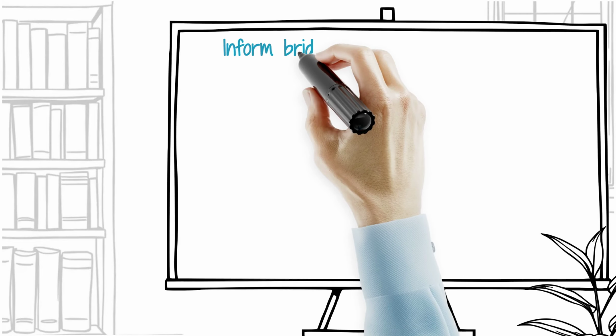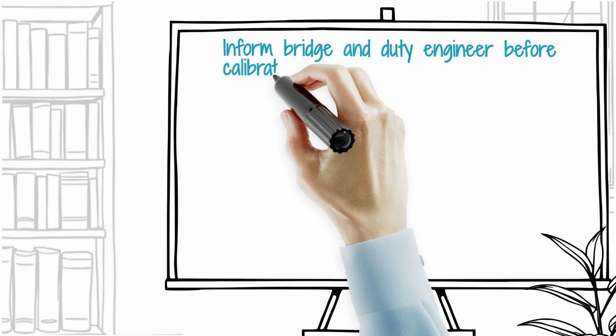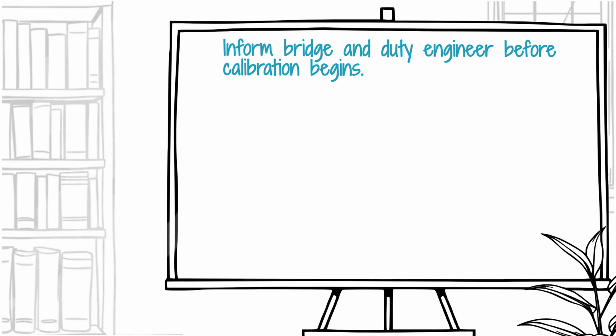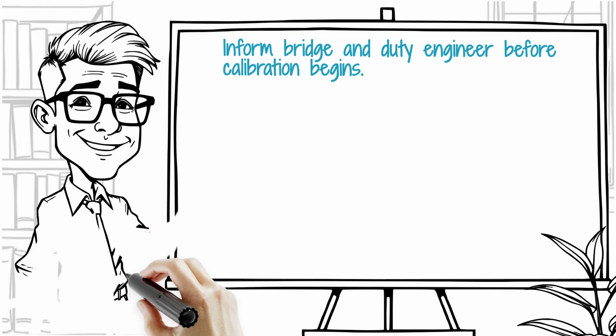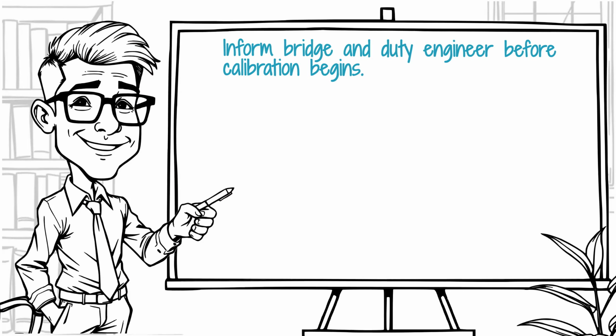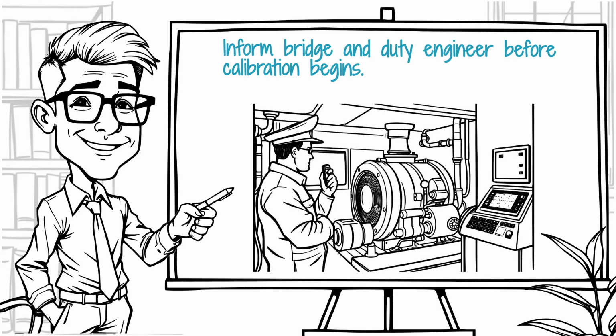Before you begin any calibration work, you must inform the bridge and the duty engineer, as the process involves deliberate interference with the boiler's safety interlocks. Ensure the boiler is under steady load and that you have a clear view of both the local gauge glass and the remote control room display.